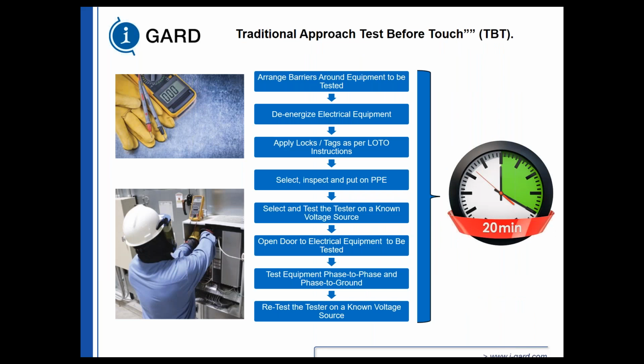So what we have to do is arrange the barriers around the equipment to be tested, de-energize the electrical equipment, apply locks and lockout tagout as per the instructions, select and inspect the PPE. So even before we put on the PPE, we're working outside the cell. We don't really require the amount of PPE because we're working with the doors closed, operating on gear which is supposedly functioning properly and shows no impending signs of a fault. We don't necessarily need to put on the PPE.